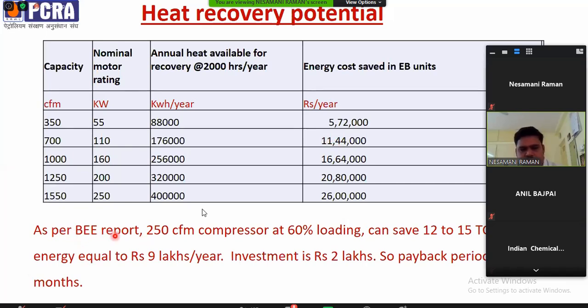As per a BEE energy audit report, a 250 CFM compressor at 60% loading, because no compressor will always be at 100% load, the load will be varying continuously. So for optimum, we have taken 60% loading. It can save almost 12 to 15 tons of oil equivalent per year, which is equal to almost 9 lakhs per annum. The investment cost of the heat recovery system in the compressor is 2 lakhs. So the payback period is around 4 months.